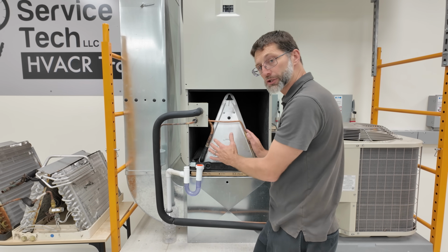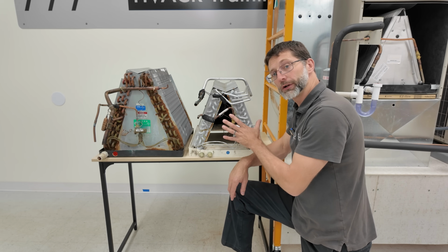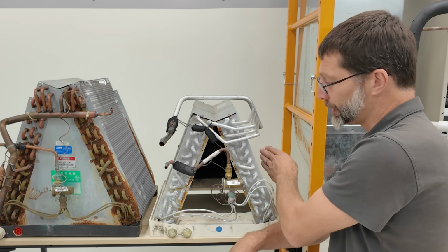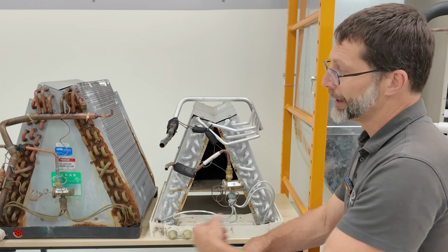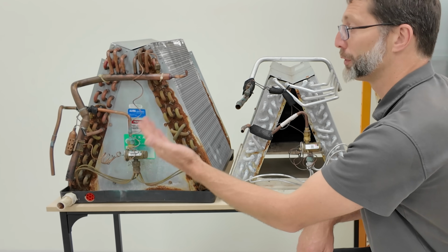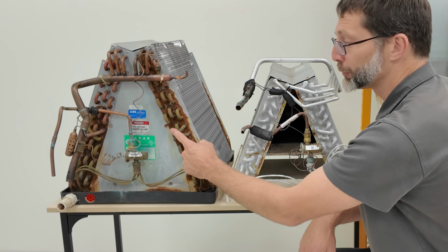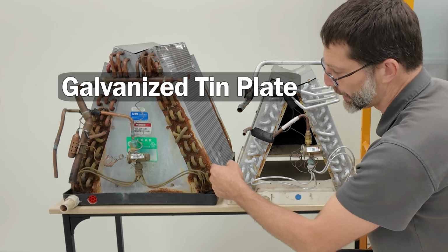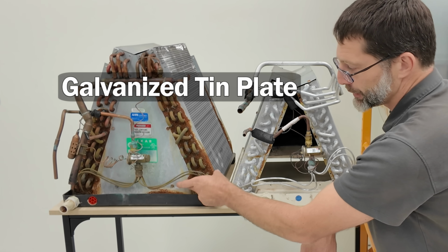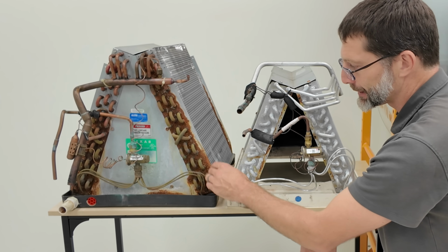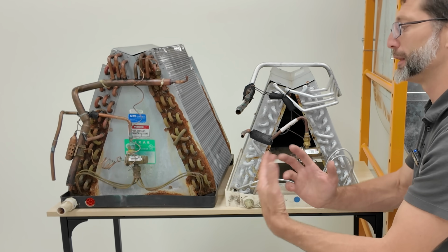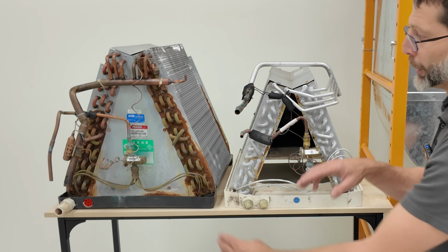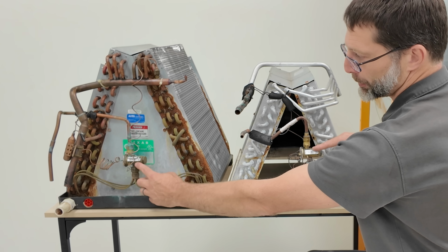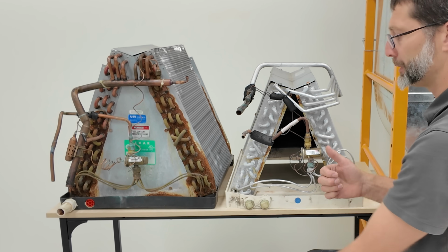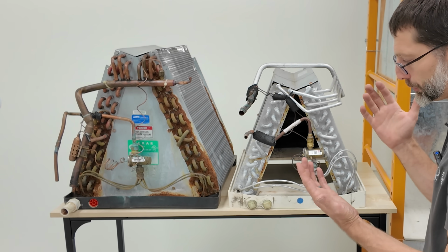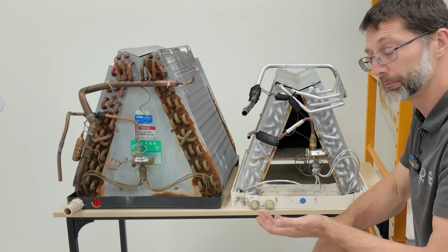So this is a microchannel coil, whereas this one right here is an aluminum tube and aluminum fin, and it has an aluminum plate. And this is the older conventional one where you have the copper tube and aluminum fin with the galvanized plate. A lot of times these rust and you end up having a leak down here at the lower section, so that's been an issue. Both of these have thermostatic expansion valves instead of a piston metering device like we were looking at on the previous example, but the premise is still the same.